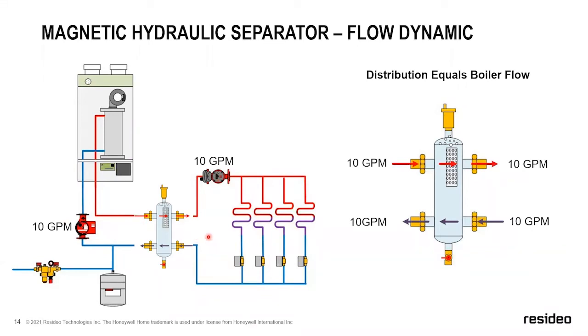So if you look at any modern high efficiency modulating or condensing boiler, you're going to see that they're going to want you to draw it out with some form of hydraulic separation. So they'll a lot of times draw it with closely spaced T's, and it'll put an asterisk that says a low loss header is an acceptable means as well. But what you need to do is create a difference of flow characteristic between the two systems.